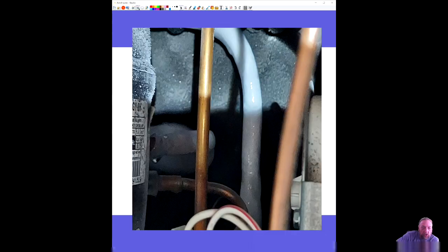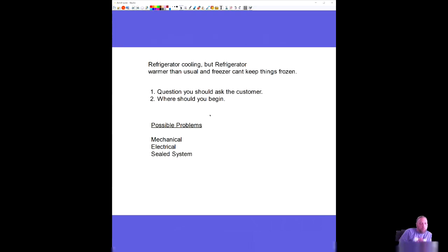Well, you could have had a bad hose, or even inside the micron gauge, there's a seal in there, and believe it or not, these micron gauges work off of thermistors when they pull a vacuum. And if they get dirty or oil in them, it messes up the accuracy of the micron gauge.